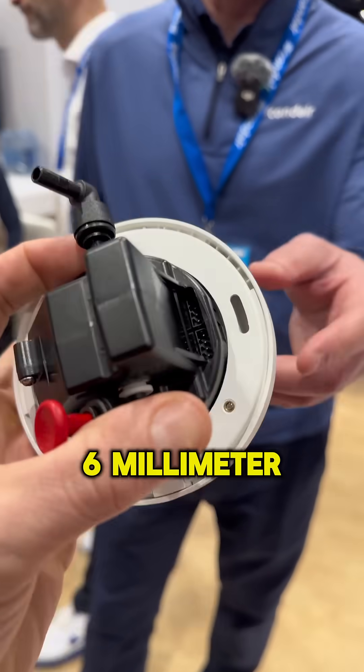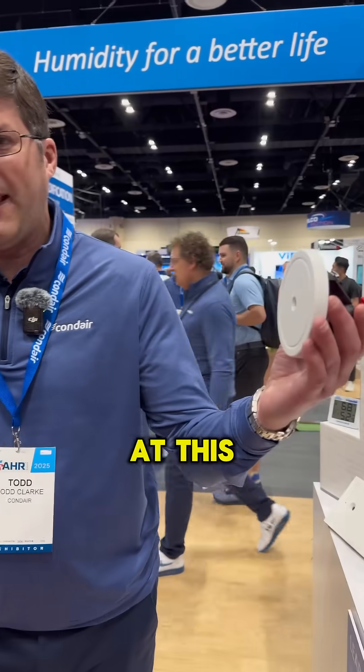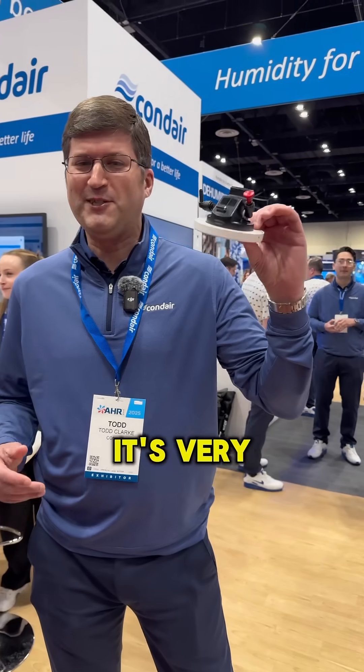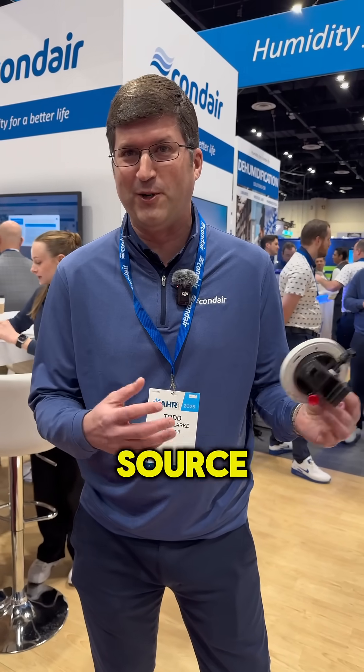We run a six millimeter John Guest water line in conjunction with a data cable to each one of these spray head locations. At this head location, we're converting water from liquid to vapor through a mesh nebulizer. It's very similar to ultrasonic technology — it uses a piezo element, so it uses vibration and frequency to convert water from liquid to vapor right here at the source.